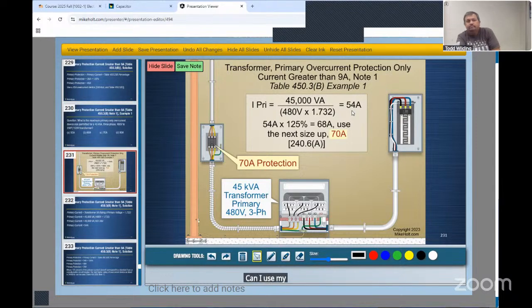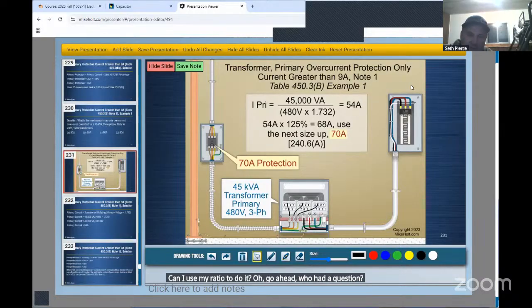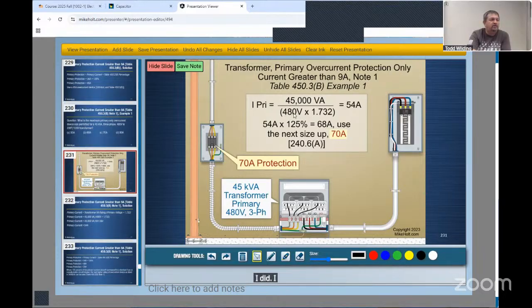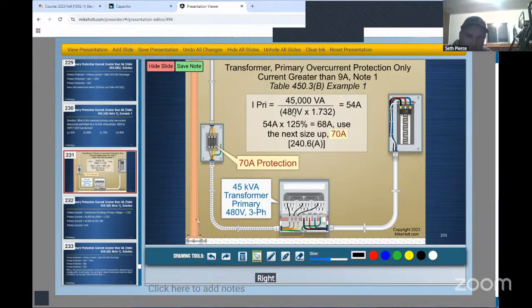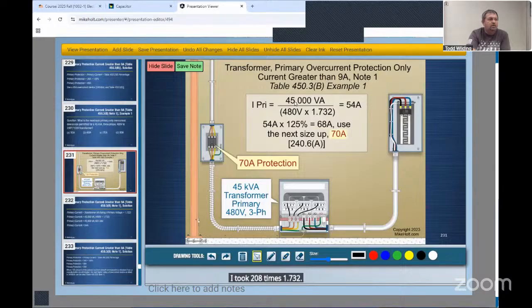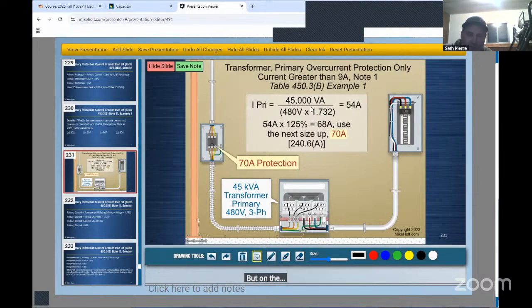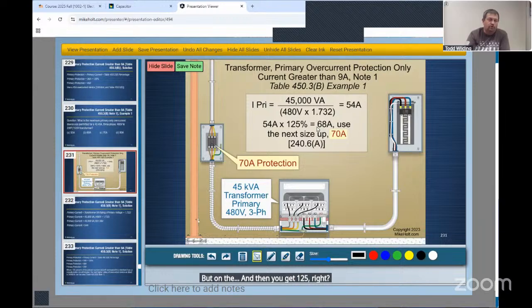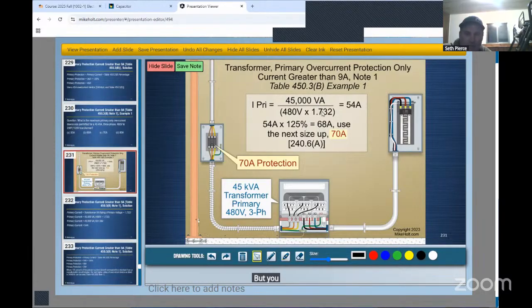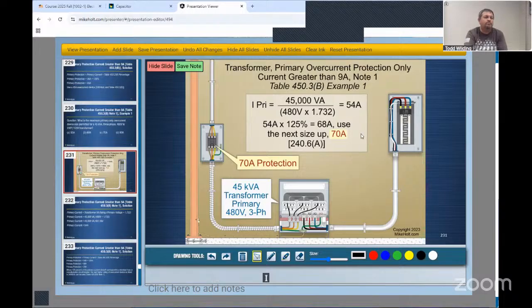Can I use my ratio to do it? Oh, go ahead. Who had a question? So you didn't times it by 1.25% then on that other one? I did. I took 208 because I want to know the secondary amperage. I took 208 times 1.732 and divided 45,000 into it, and then you get 125, right? 124.5 or something like that. But do you not times it by the 125%? I didn't, no, because I'm just doing power in and power out. This is my power in. So I've got to have that same amount out, so I've only got 54 amps, right?